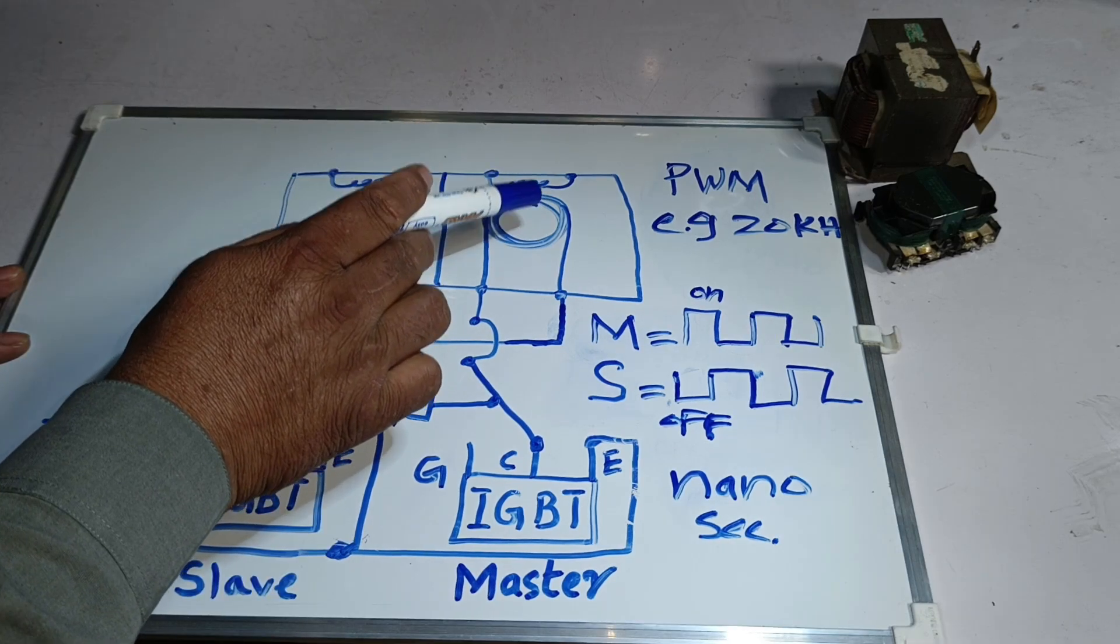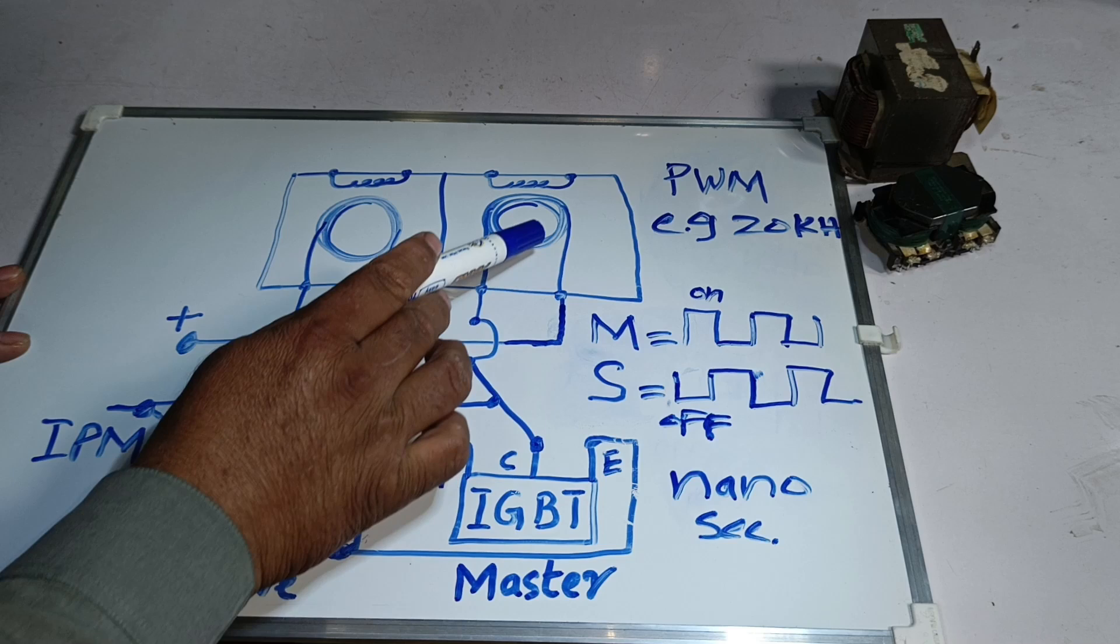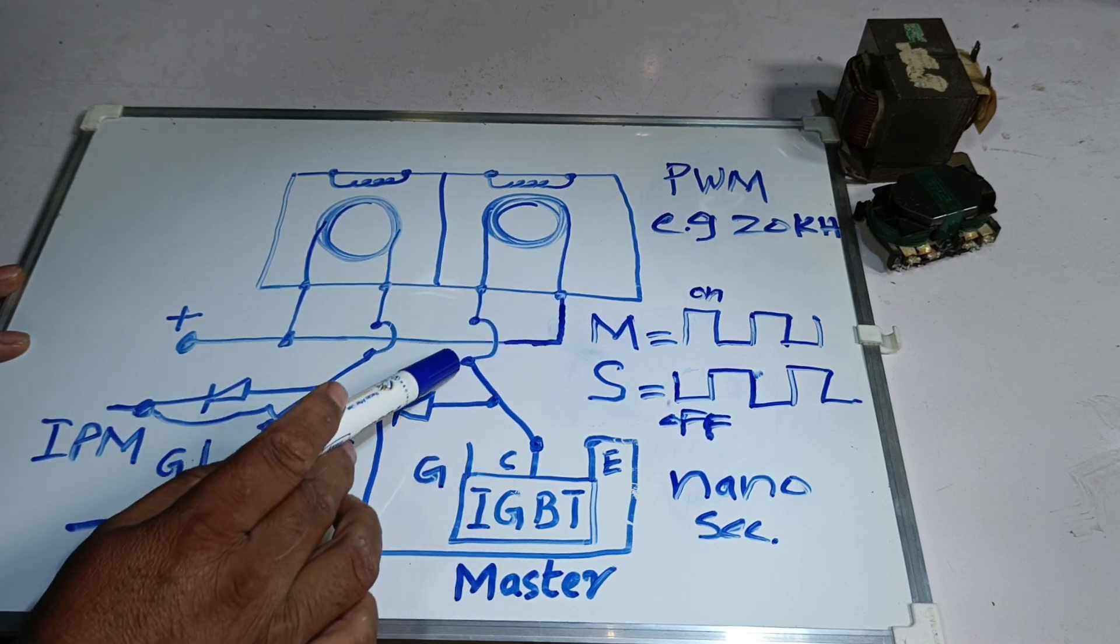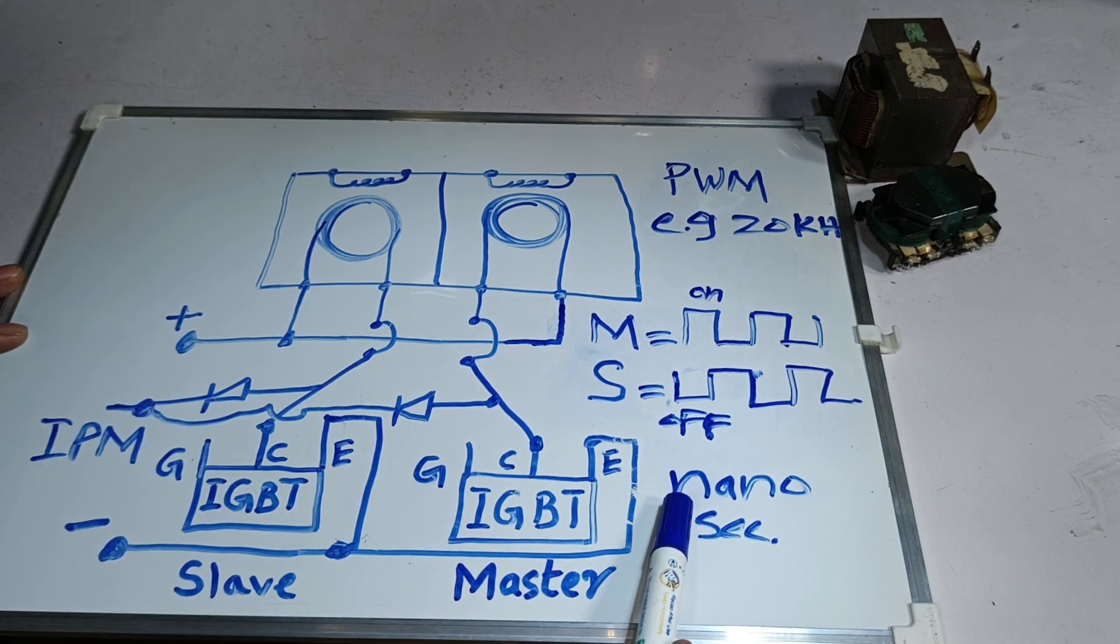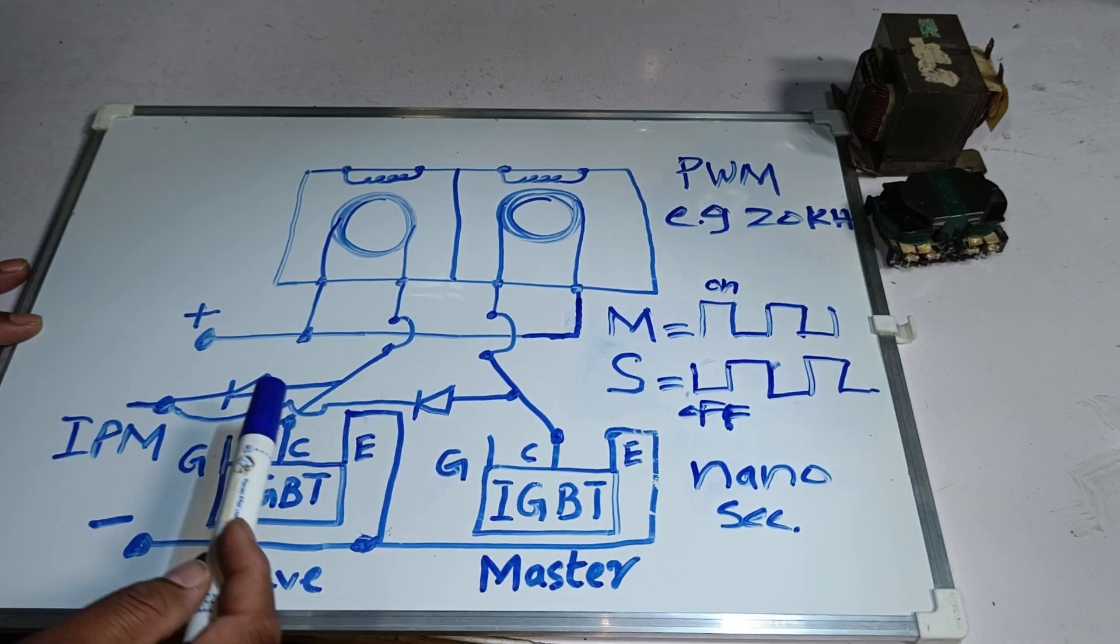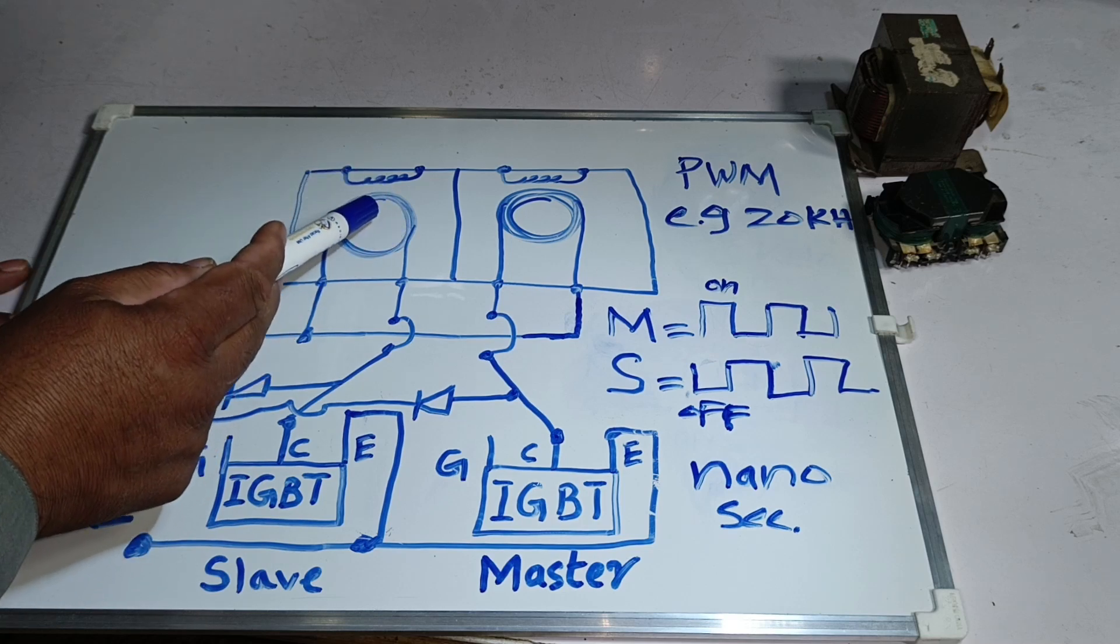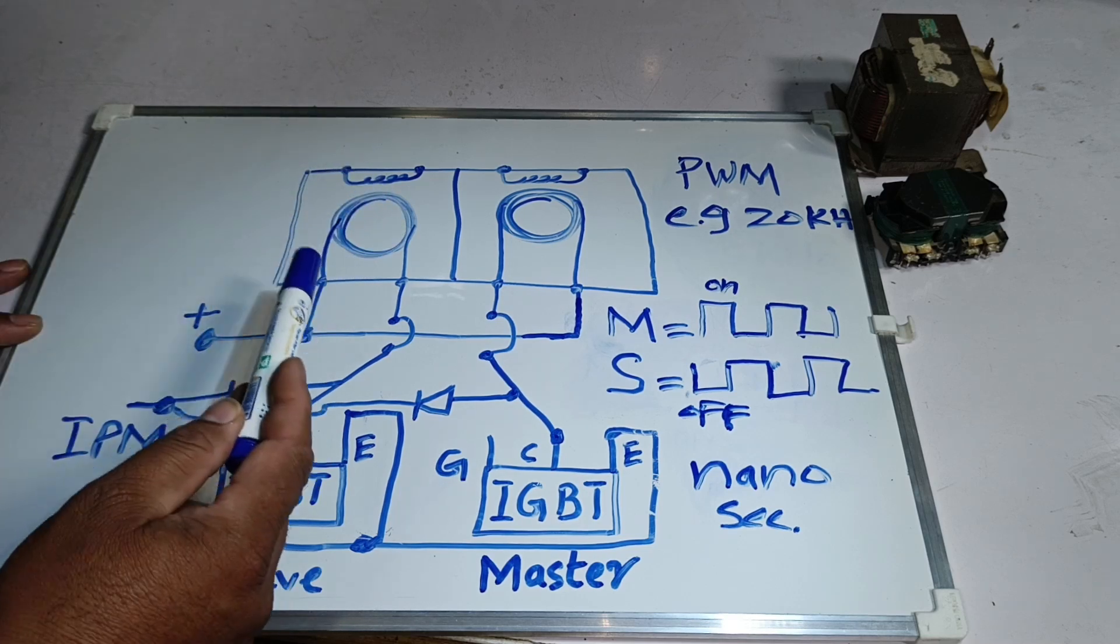This current flow causes the master reactor to charge, storing energy as a magnetic field, while the slave reactor will remain in the off position. As soon as the master reactor charges, the master IGBT will turn off, and the charged current will flow towards the diode, which will direct it to the IPM. A few nanoseconds later, the slave IGBT will turn on, causing the slave reactor to charge. It will then discharge, and the cycle will continue.